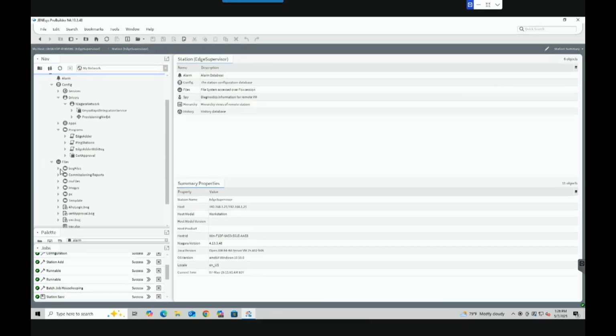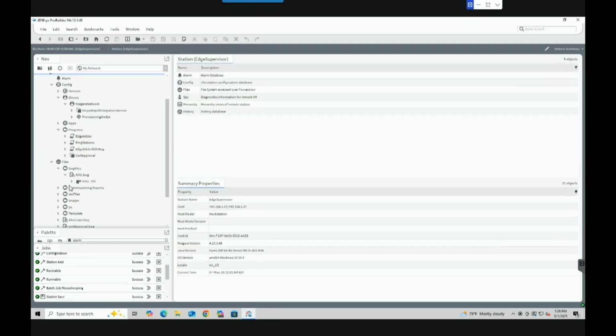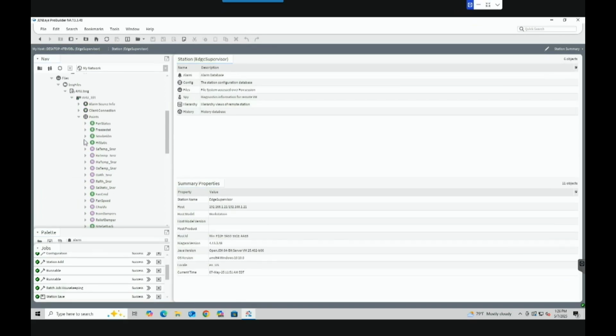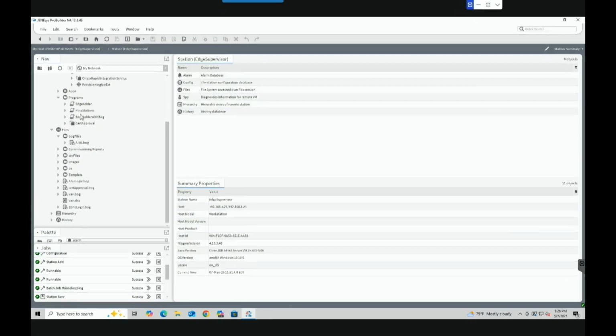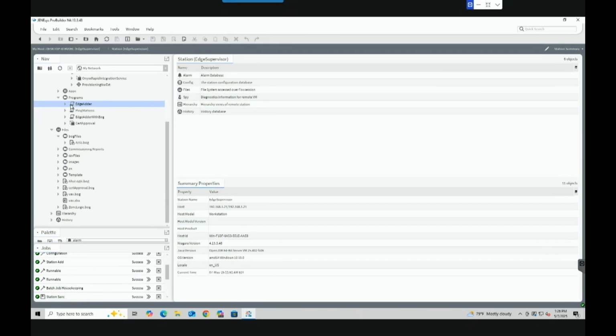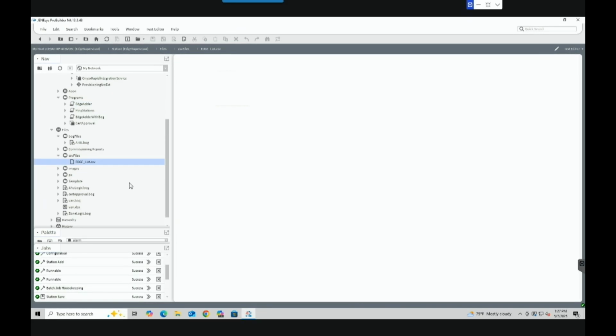So as I have here in the file space, I have this AHU bog, and under here we can see it as a Niagara Edge station. It has just AHU 101 because that's what I had before, and underneath I have a bunch of points. So the first program object, if I just double click and go to the property sheet, we can see I can select from any CSV here, which I've already imported into a folder called CSV files. Now again, you can do Microsoft Excel and turn it into a CSV file if you want to.